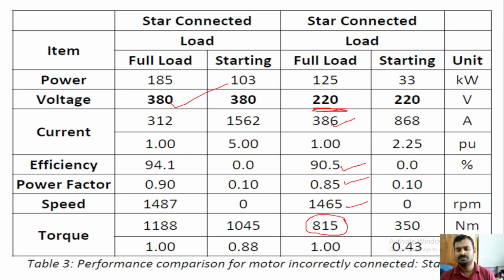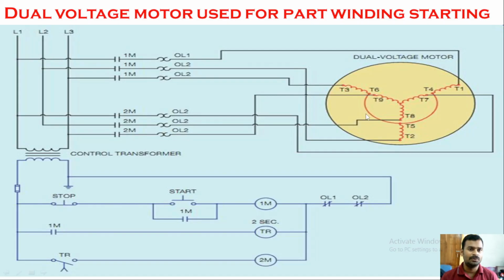This means the load handling capacity of this particular motor is going to be reduced, and if you give extra load, then the motor speed will be reduced drastically. At one particular stage, the motor will stall or it will not run. So this is the problem with connecting a motor in star with a low voltage configuration for this particular motor. I am just giving a comparison for this particular motor. This is how the performance will be affected. And now let us see how the motor connection is taking place.